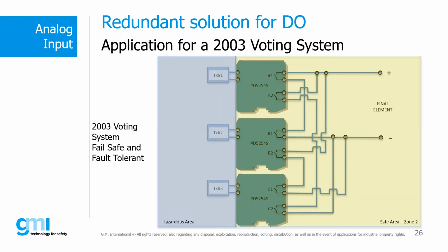The three trip amplifier devices each have 2 alarm relay outputs with individually programmable thresholds, and each of them is SIL2. By programming all the alarm thresholds of the trip amplifiers in the same way and connecting the relay outputs as we see in the slide, in such a way as to compose a matrix of contacts, we can obtain a SIL3 level from SIL2 components. To activate the final element, at least 2 of the 3 loops, sensor plus trip amplifier, must perform the same variable measurement in the field and correctly process the data.